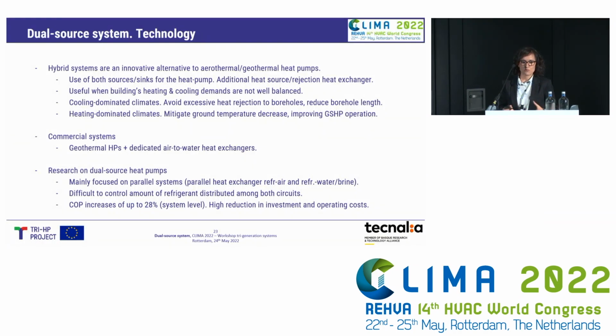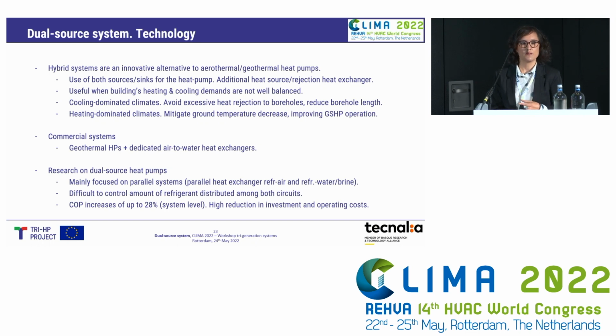So, starting with the background of this technology: hybrid systems are an innovative alternative to either aerothermal or geothermal heat pumps, meaning they can use both sources or sinks for the heat pump. Normally a geothermal heat pump is used, where an additional heat source or rejection heat exchanger is added to the system. These systems are useful especially when buildings' heating and cooling demands are not well balanced.